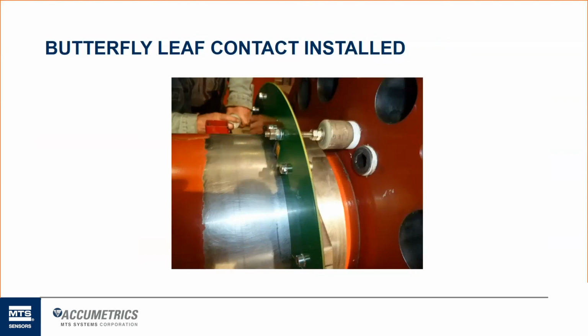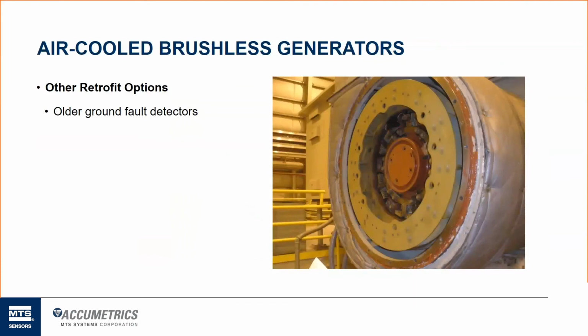This shows the collar mounted to the steel of the rotor itself. Again, we need the utilities to have a good clean surface for us to mount, because this is how we pick up that electrical ground connection. They've done a very good job here. They probably removed a little more paint than would be necessary. We usually just need it right underneath where our steel has to bolt to the shaft itself. But this was a customer that did a very nice job for us. So that was an example of the larger hydrogen cooled machines.